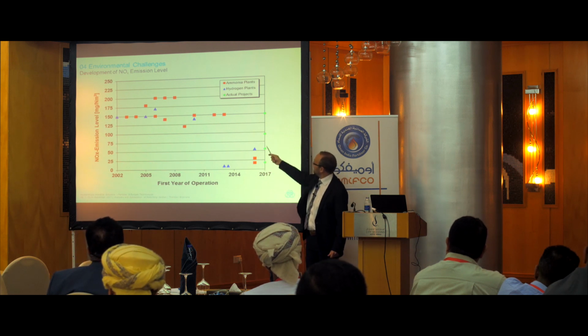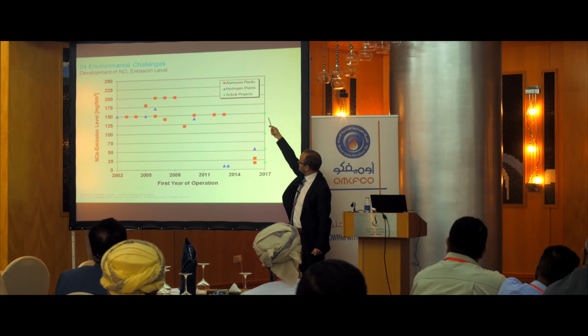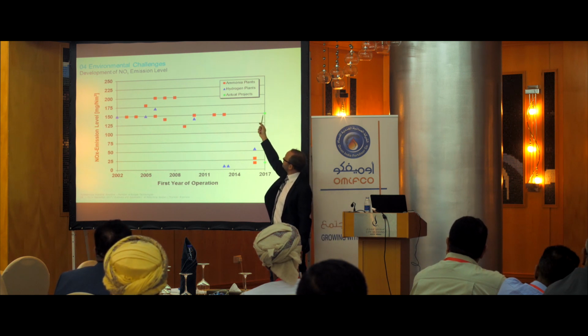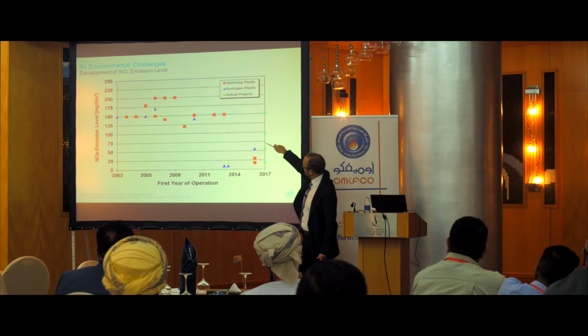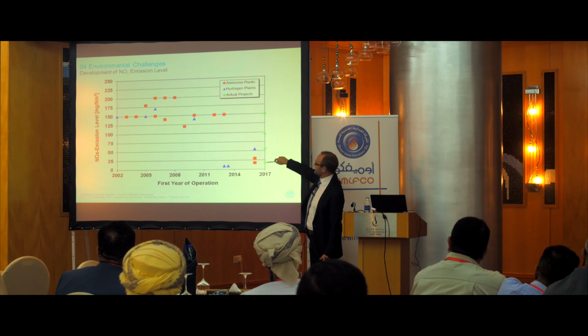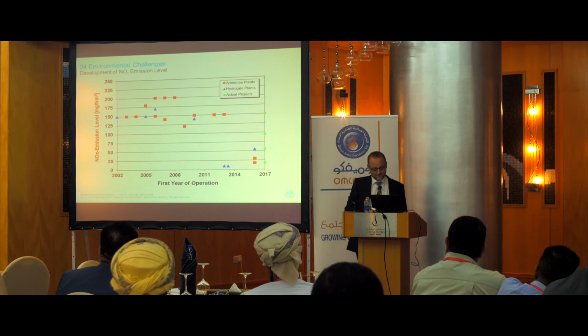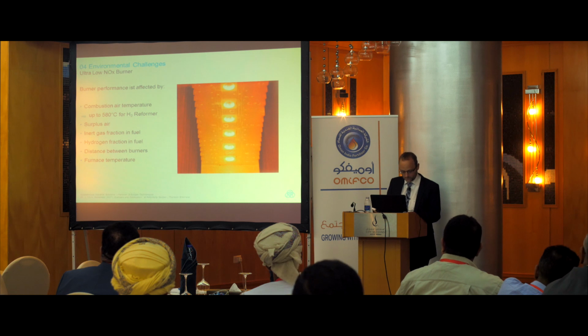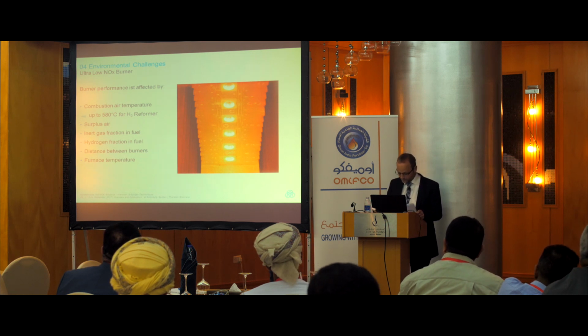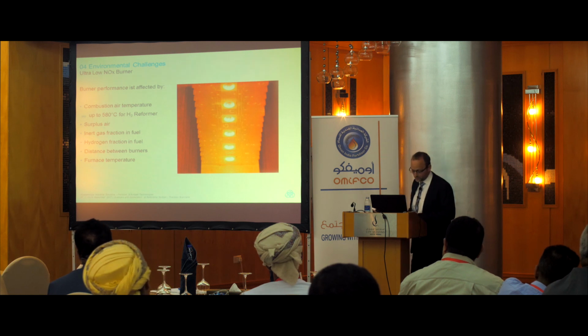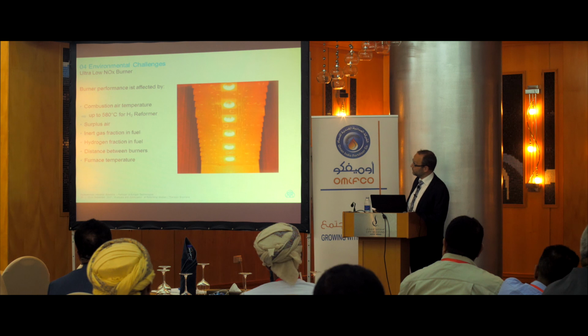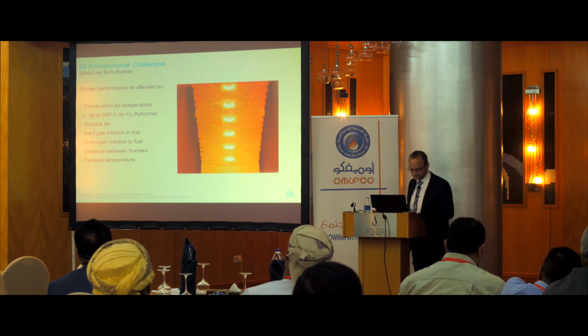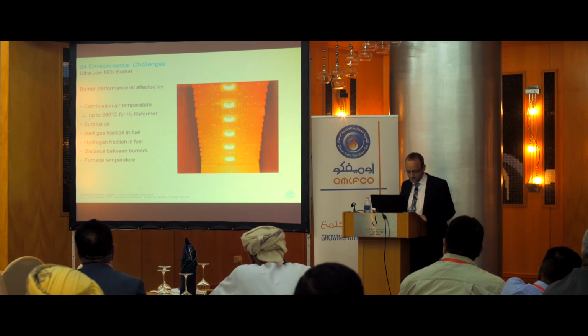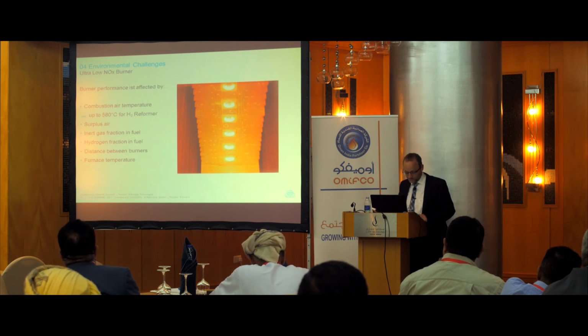In green, I added plants we are working on right now. So we have, of course, still plants which have a quite high level, but also plants which are also here in the region less than 10 ppm NOx in the flue gas. As a first option, I will talk about the use of the latest burner technology. These burners are called ultra-low NOx burners. The performance of the burner itself is of course affected by several process parameters as shown here, especially combustion air temperature and fuel composition.